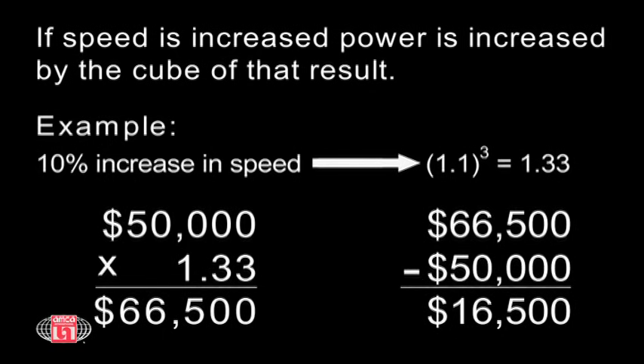Or consider a second example of a 100 brake horsepower fan that costs $50,000 per year to operate. A 10% increase in speed to compensate for system effect will result in an over $16,000 operating cost increase per year. And that's just for one fan.